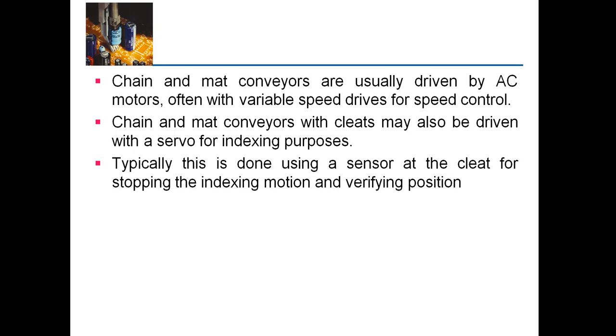The chain and mat conveyor is usually driven by an AC motor, often with a variable speed drive for speed control. Chain and mat conveyors with cleats may also be driven by a servo for indexing purposes. Typically this is done using a sensor at the cleat for stopping the indexing motion and verifying position — the sensor verifies position and stops the motor at a very precise location, which is why it is called indexing motion.